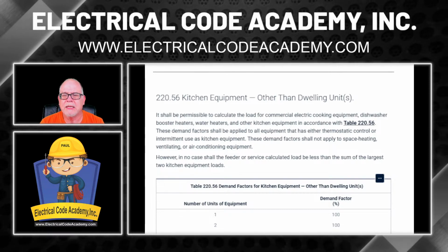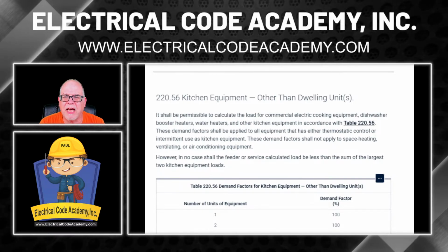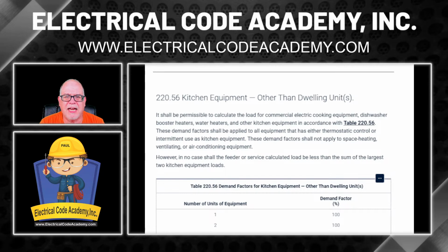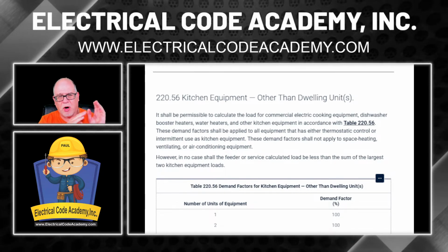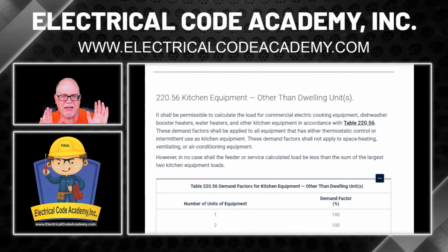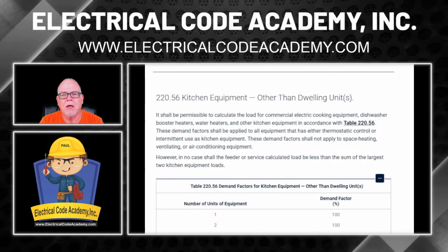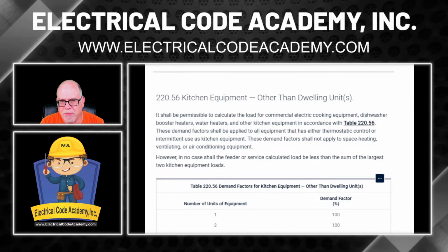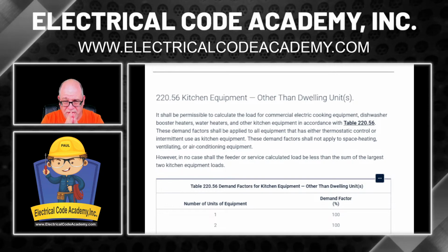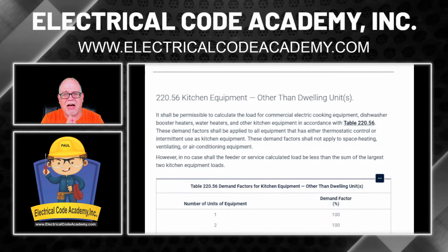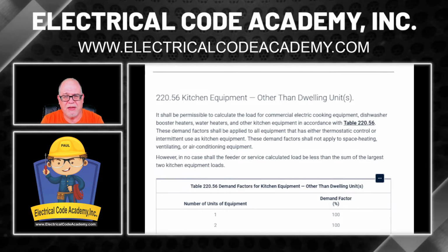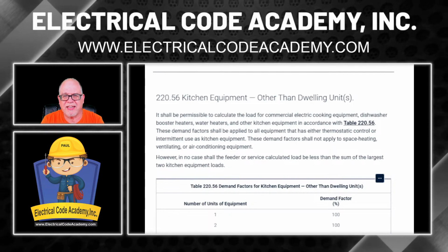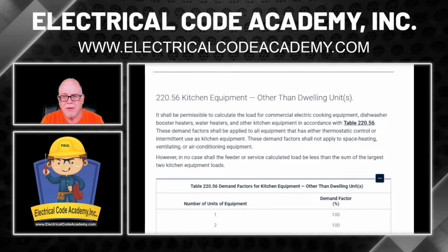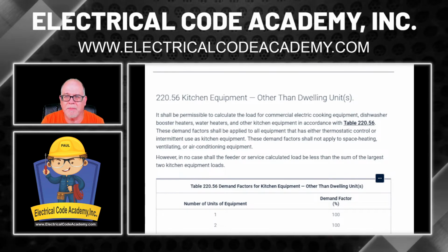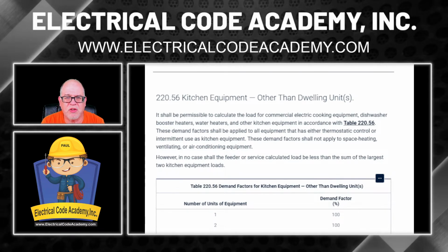So we're good with all these pieces of equipment. It also says these demand factors shall not apply to space heating, ventilating, or air conditioning equipment. Yeah, because we got our own rules for that. So not going to have anything to do with that. Okay. One of the most important aspects I want you to be aware of is where it says, however. It says, however, in no case shall the feeder or service calculated load be less than the sum of the largest two kitchen equipment loads.